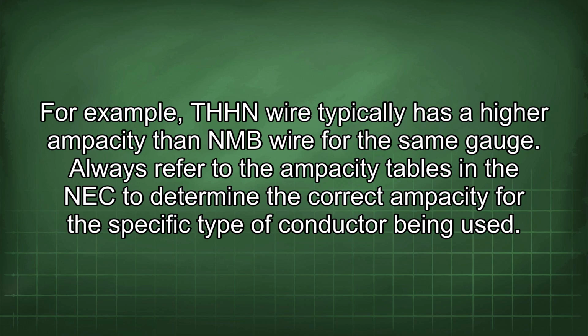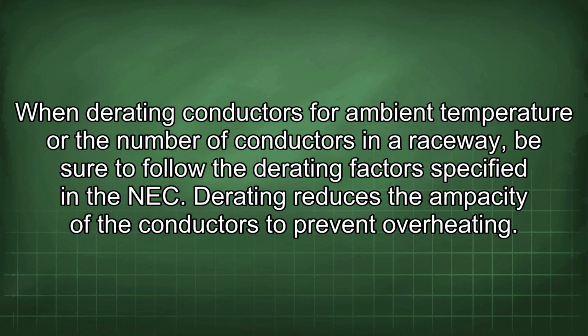Always refer to the ampacity tables in the NEC to determine the correct ampacity for the specific type of conductor being used. When derating conductors for ambient temperature or the number of conductors in a raceway, be sure to follow the derating factors specified in the NEC. Derating reduces the ampacity of the conductors to prevent overheating.